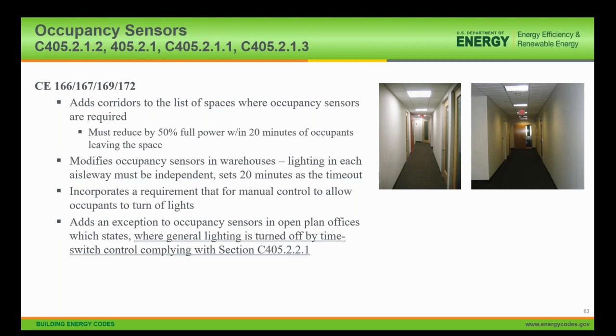You must now do them independently, and that they have to have a 20 minutes timeout. That's because many times people may only be in one aisle and not all of them, and therefore you can dim down those other aisles when people are not in them at the time. And also, occupancy sensor changes also incorporated a requirement that manual control allow for occupants to turn off the lights.